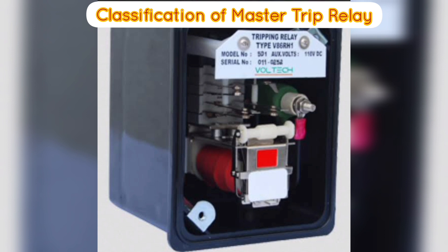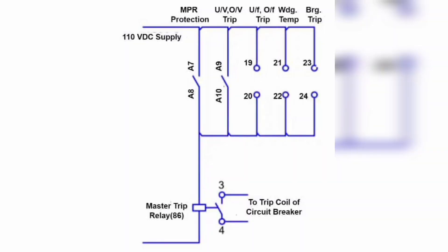Medium Level Master Trip Relay, ANSI Code 86M: When the generator is running in synchronization with the grid supply, and faults such as overcurrent, instantaneous overcurrent, and earth fault occur at the grid supply, then the generator should isolate from the grid supply. This is what the Medium Level Master Trip Relay does. The relay first trips the grid breaker, and if the fault level is still high, it trips the generator breaker. Also, in the case of mechanical failure of generating station equipment — such as oil pressure low, ACW (auxiliary cooling water) flow low, or MCW (main cooling water) pressure low — the Medium Level Master Trip Relay trips the generator breaker and enunciates the alarm, thus isolating the grid supply from the generator supply.